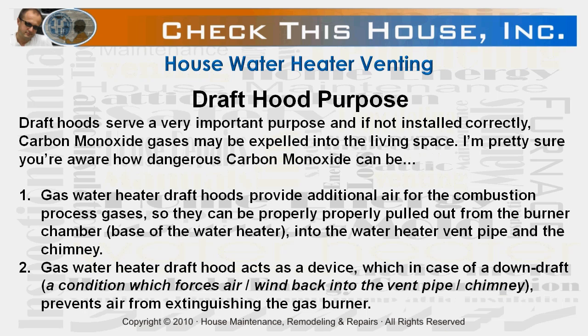The first purpose of the gas water heater draft hood is to provide additional air for the combustion process gases so they can be properly pulled out from the burner chamber, which is at the base of the water heater, and into the water heater vent pipe and the chimney. The second purpose of the draft hood is to act as a device which, in case of a downdraft — a condition which forces air and wind back into the vent pipe and the chimney — it prevents air from extinguishing the gas burner.